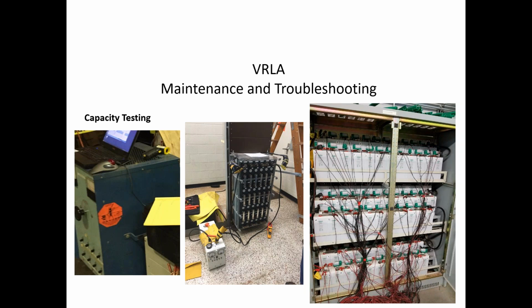Conversely, an emergency lighting battery, a telecommunication battery, or another battery that's designed for, say, 8 hours. Well, you're not going to run an 8-hour load test, but the industry standard on that size battery is typically 3 hours. So long duration battery application, 3-hour load test; short duration battery, anywhere from 15 to 60 minutes.